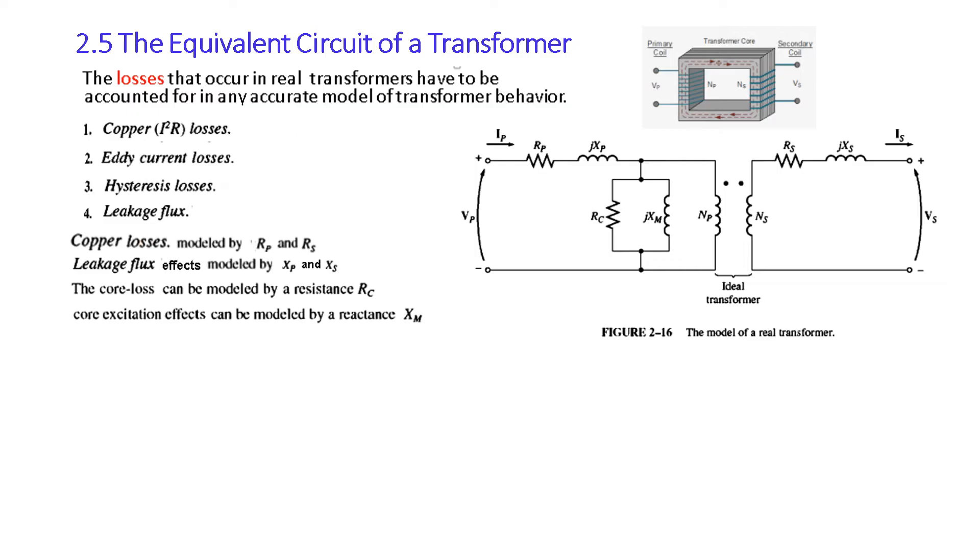Now the copper losses can be modeled by resistance Rp and Rs as I have been shown here. Copper losses are mainly, they generate heat, resistive losses. Then the leakage flux effect can be modeled by Xp and Xs. So these in series are the effect of leakage flux. Then the core loss can be modeled by Rc in parallel. So this is the core loss in parallel. And then core excitation effect can be modeled by Xm. So this is due to the core excitation. So these are the eddy current and hysteresis losses combination.